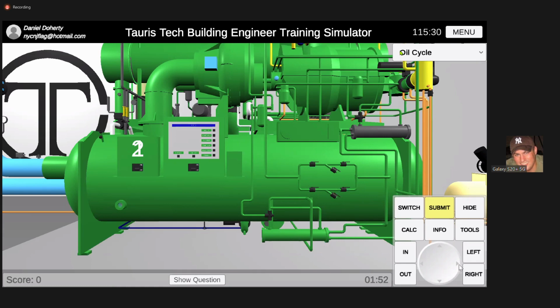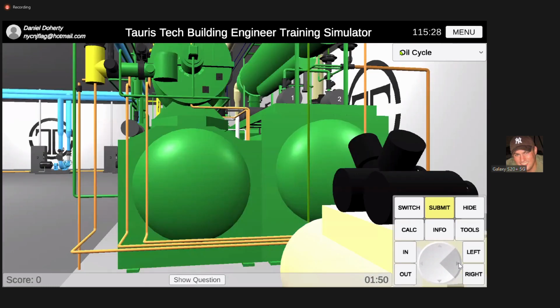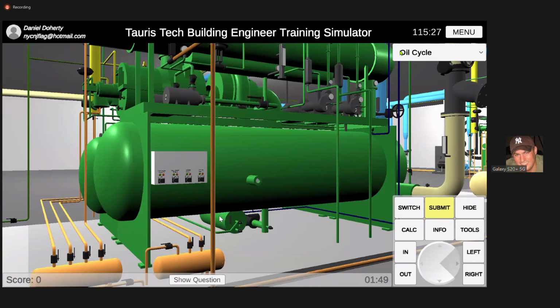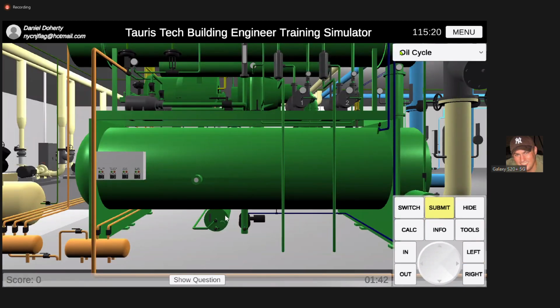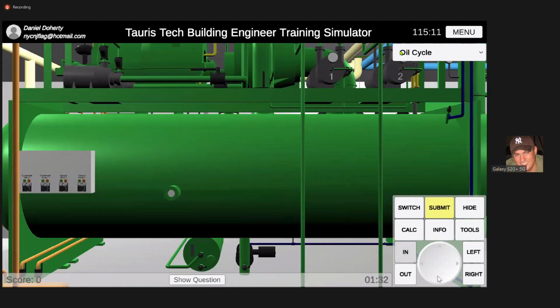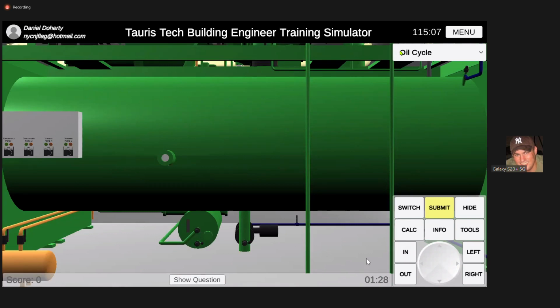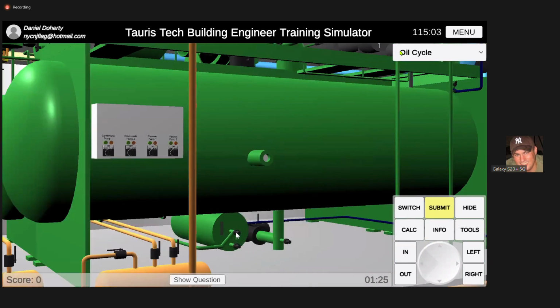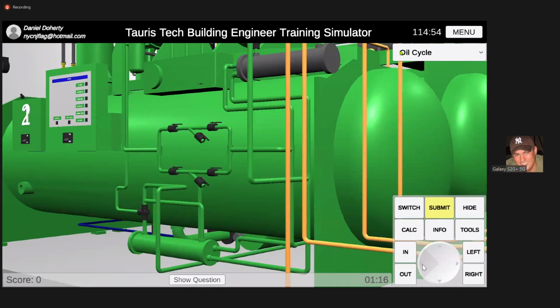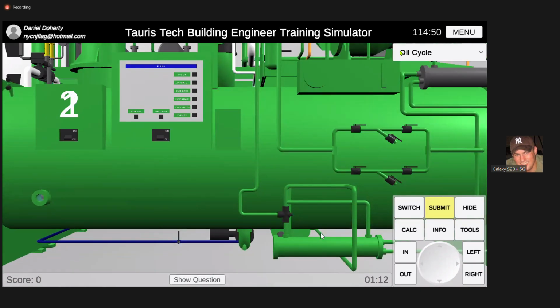Now, on the bottom, you got the oil coming in. Now, this is your compressor oil sump, okay? It's not a compressor and turbine oil sump. This is just for your compressor and nothing else, okay? So the oil comes out your sump. This is your supply valve that you can put on and off. This is normally front seated. The oil comes out, goes underneath. See the line? Comes under the heat exchanger, comes back up, and then it goes to this thermal valve right here, okay?